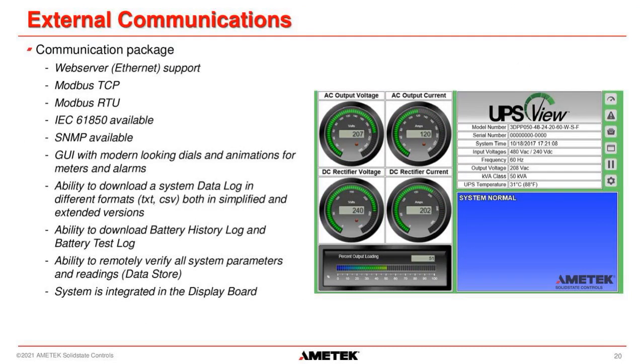The communications package that we offer includes a web server, so you can view the status of the UPS from any web browser connected to your network. We have Modbus TCP for reading voltages and currents, and Modbus RTU, which is the same as TCP with just a different connection method. Modbus TCP uses Ethernet, and Modbus RTU uses an RS-485 serial communication. I want to say all of our communications with the outside world are one-way only, except for SCI Link, where you have to be physically next to the UPS. Anything that could happen remotely will not allow any settings to be changed remotely. We also have an option for SNMP communication.